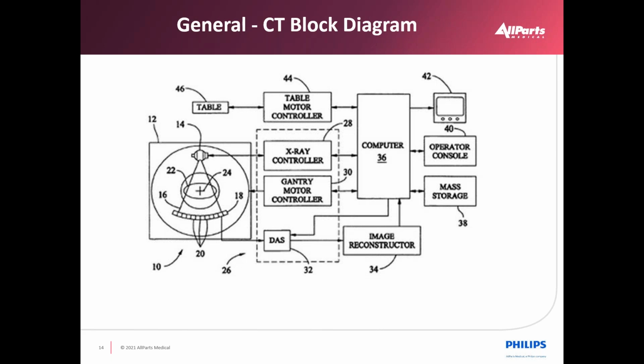So we will talk about that. With regards to the table, remember we're moving the table in and out and vertically rotating the table to center the patient. So the center crosshair you see in the gantry here, item number 24, is known as isocenter. That is the location in the gantry where you have the best image quality, the best resolution. And as things move out from isocenter, the resolution will degrade slightly. And when I say slightly, it's very, very minute, but it does happen, simply because isocenter has the best image resolution possible.